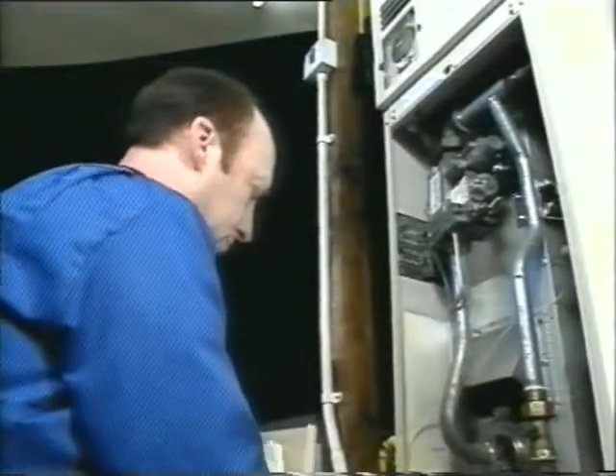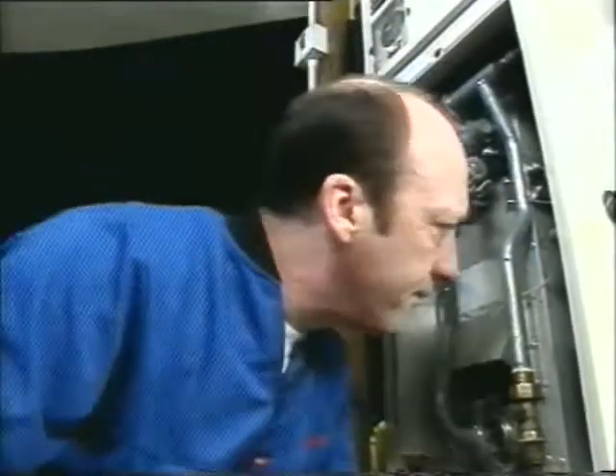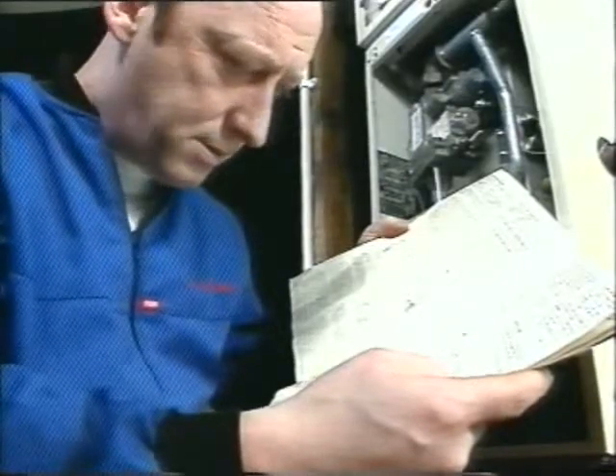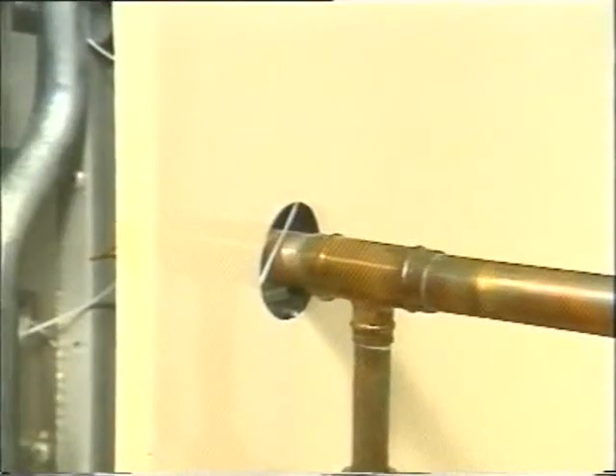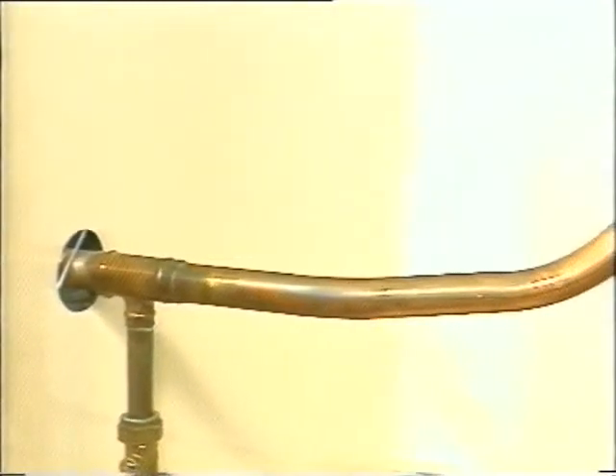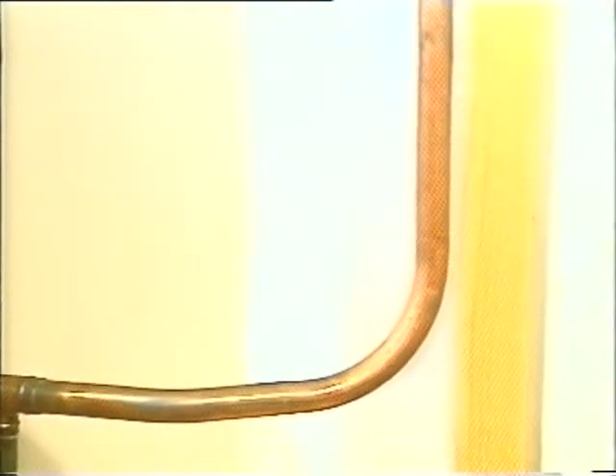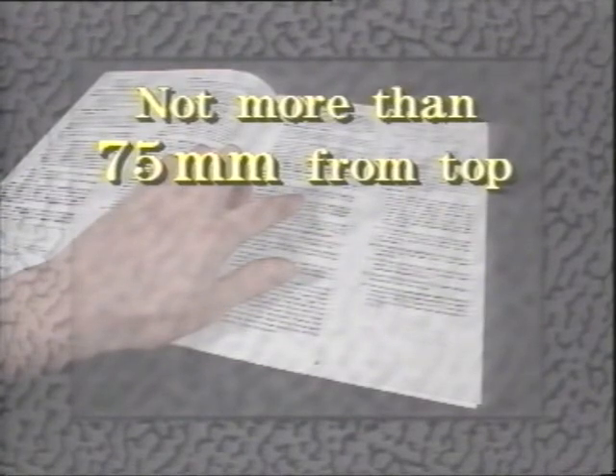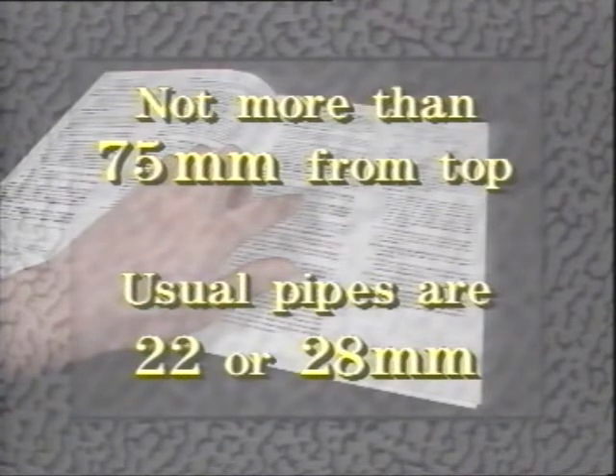When you're installing a circulator, as with all other appliances, make sure you comply with all the relevant regulations, and that includes making sure that there's a big enough head between the circulator and the hot water cylinder. Be careful how you use horizontal runs. Keep them minimal. Make sure they rise 25 millimeters every 3 meters, and wherever possible, use large radius bends. The manufacturer's instructions will tell you the maximum allowed pressure head. The flow connection to the cylinder has to be no more than 75 millimeters from its top, and the usual pipes are 22 or 28 millimeter.